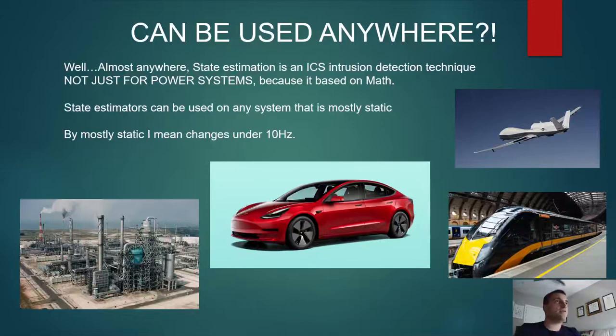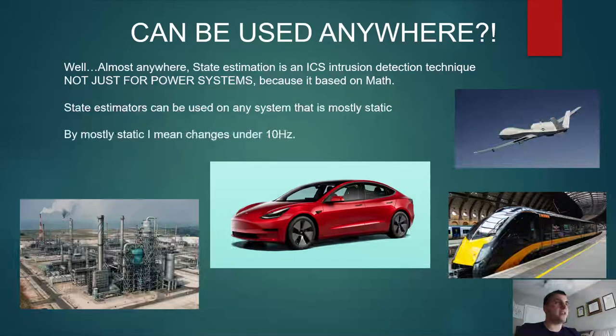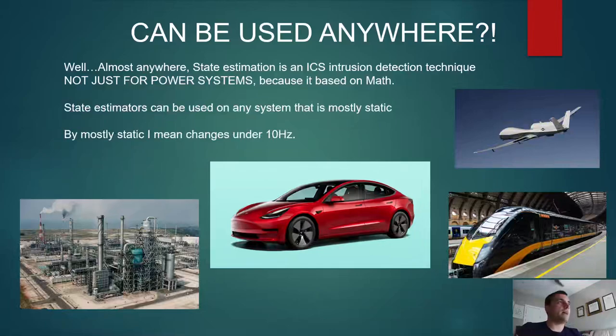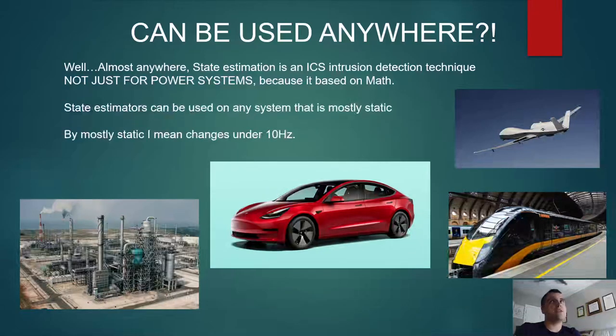It can be used anywhere because it's a numerical technique. Any system that's roughly stable and follows the laws of physics, you can use state estimation as a technique for detecting an attacker. It's an ICS intrusion detection technique, not just useful for power industry. The only real limitations are that the system needs to be mostly static. Once things start changing over 10 hertz, there's research into dynamic state estimation, but it's by no means a well-established technique.